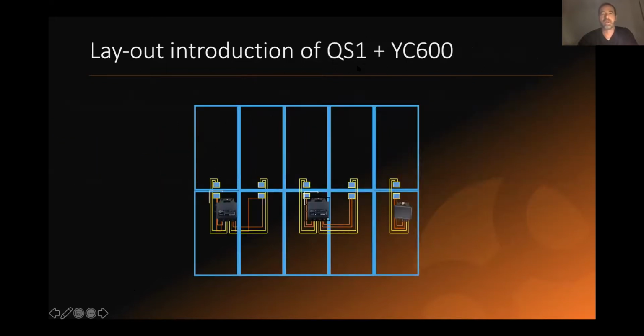QS1 is a quad, same story, except it's with 4 panels. The good thing is that the QS1 and the YC600 are compatible. So if you have an installation with 10 panels, you can use either 5 YC600, or 2 QS1 quads for 8 panels and for the remaining 2 use a YC600. And if you have only 9, you can use YC600 and just put a cap on one of the DC connectors, and you're good to go. So a lot of flexibility for design and installation.